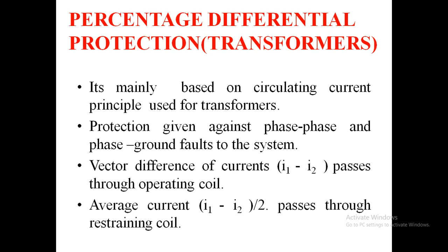So here, this is the comparing of the current entering and leaving of the transformer. This is represented by the vector sum difference I1 minus I2 which passes through the operating coil, while the average current (I1 plus I2) divided by 2 passes through the restraining coil. In normal condition, these two currents at the two ends of the transformer are equal and balanced.